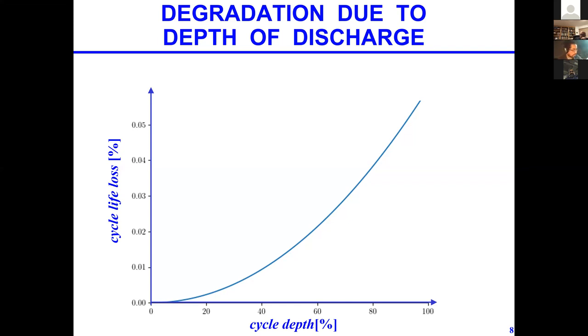So as you use it, the storage capacity in energy units starts to decrease continuously, slowly, and this is trying to account for that, saying if you keep doing cycles at this much, you're going to lose this number of cycles. To find the number of cycles the battery can do throughout its life, they set a threshold that once the battery's maximum SOC is only say 80% of the nominal value it had when it left the factory, then that battery is done, it reached the end of its life.